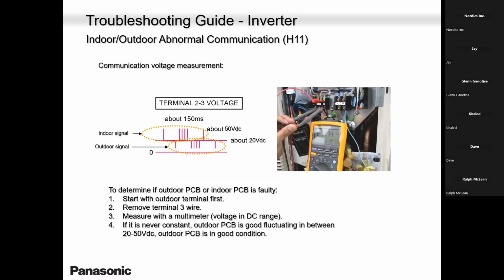So guys, when you're doing a voltage reading, a fluctuation, DC volts reading, I would strongly advise you to use this multimeter pictured here. I get calls day in, day out. Guys are using Amprobe. And when they're using Amprobe, the algorithm is a little bit different. And you will find out that the voltage reading is not good. And when you tell me over the phone, the voltage I'm getting is this, and then I'm saying, oh, I'm leaning towards the outdoor board, or I'm leaning towards the indoor board and stuff like that. Meanwhile, I'm giving you a wrong answer. So to help me out, please always invest in this kind of a multimeter.